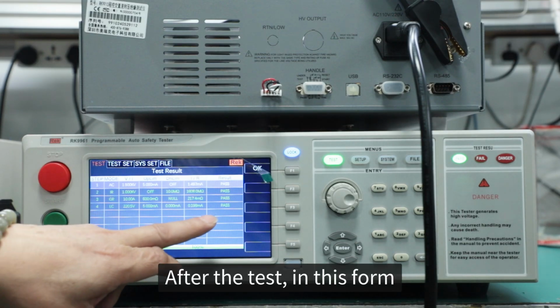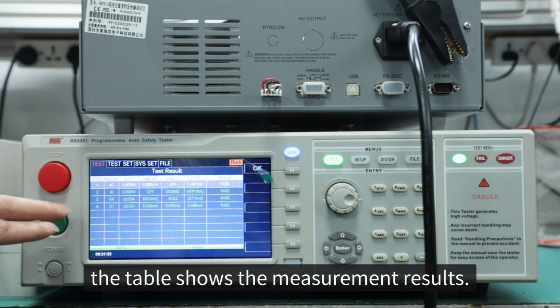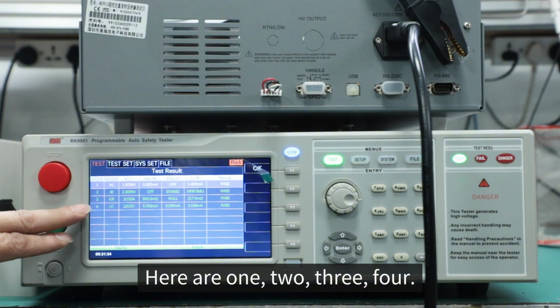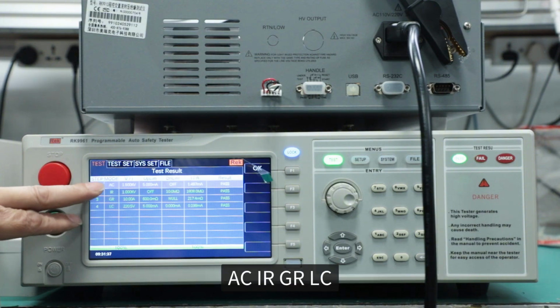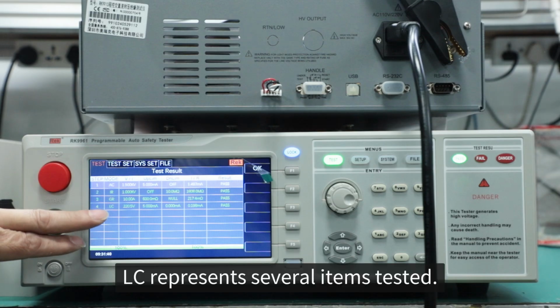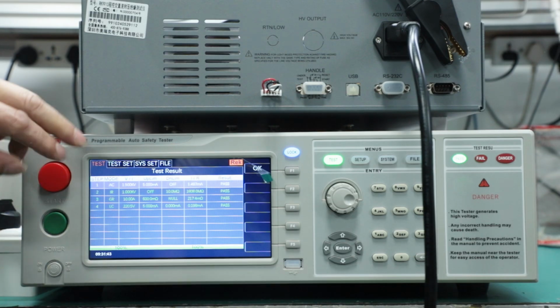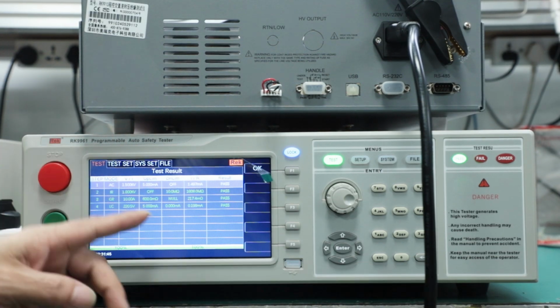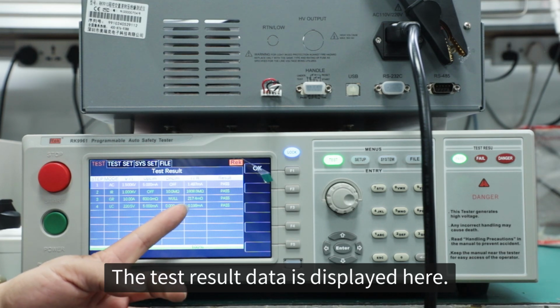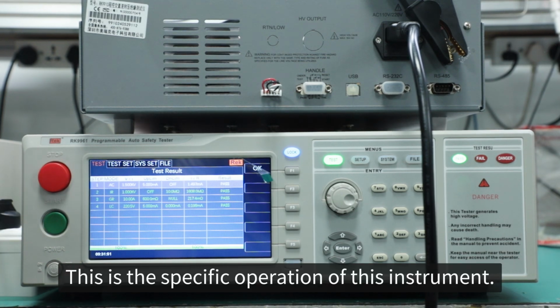After the test, the table shows the measurement results. Here are 1, 2, 3, 4, the several items: ACW, IR, GR, LC. LC represents the leakage item tested. The judgment result is pass here. The test result data is displayed here. This is the specific operation of this instrument.